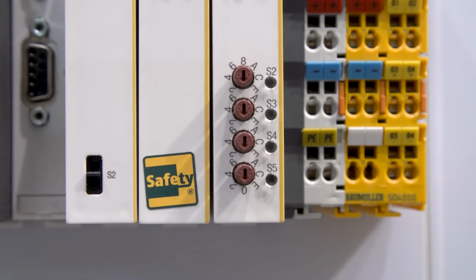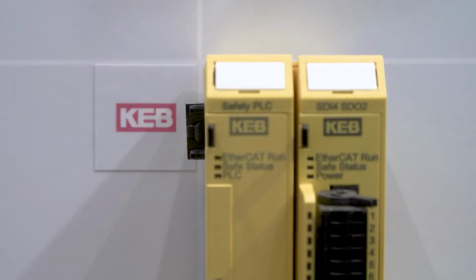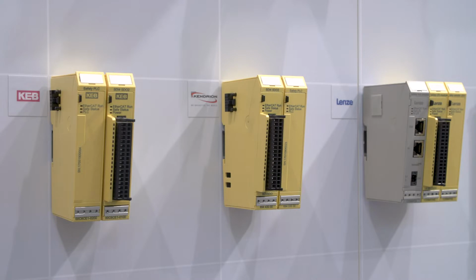With Safety over EtherCAT, functional safety can be integrated within a machine. Safety logic devices, safety I/Os, safety drives can be combined with a safety protocol. And Safety over EtherCAT can not only be transferred via EtherCAT, which of course is well possible, but also via other fieldbus systems or via Ethernet, for example, for controller-controller communication in a safe way for plant-wide safety functionality. This is due to the black channel approach, so we don't care about the underlying communication system.